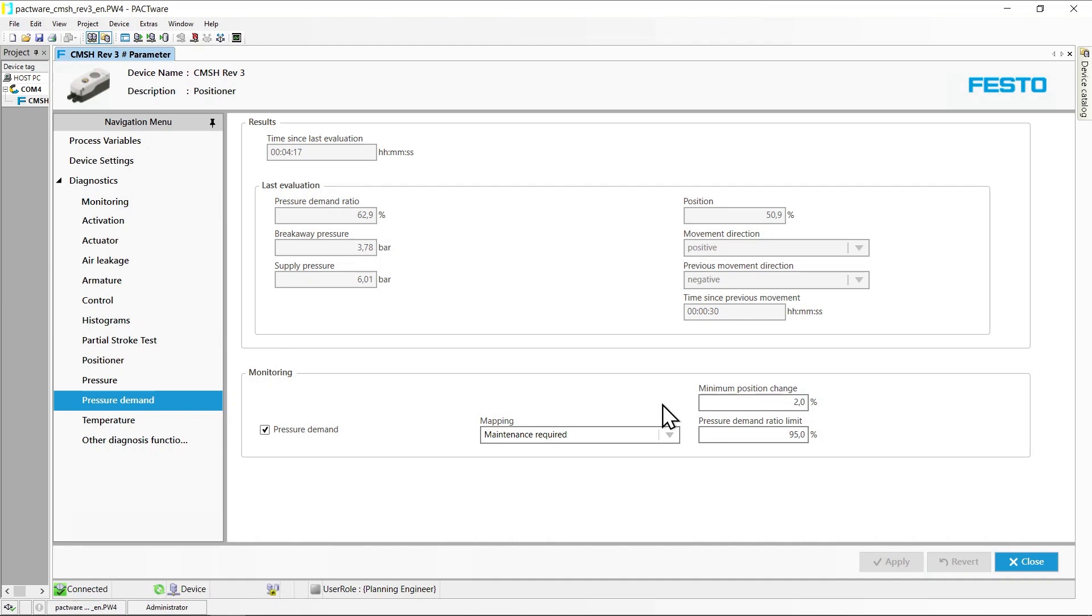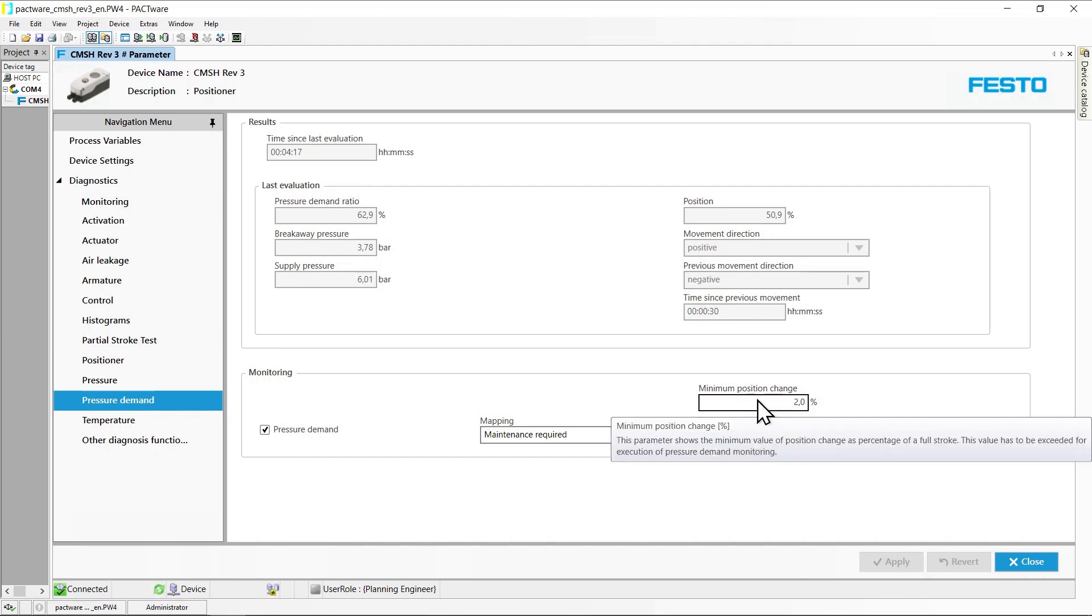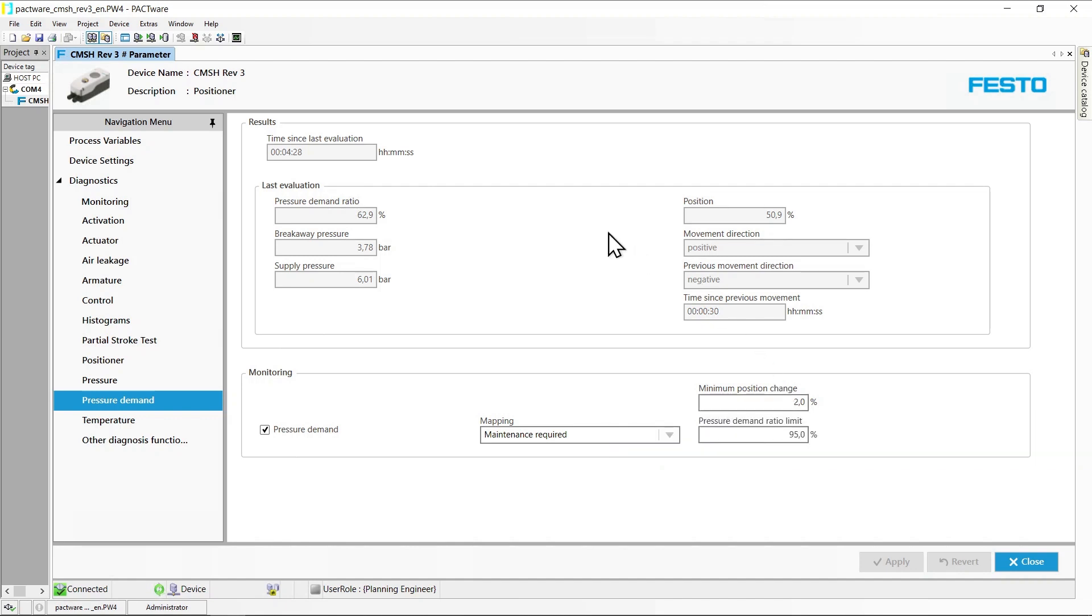Breakaway pressure difference is determined when the position has changed by more than the amount specified by minimum position change in the expected direction. In case of an abrupt start of movement, for example, an evaluation is not always possible and breakaway pressure calculation is aborted.